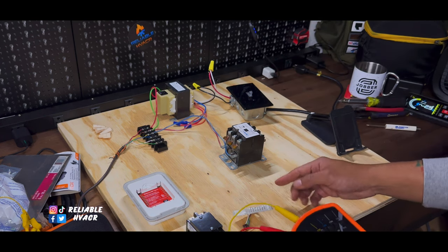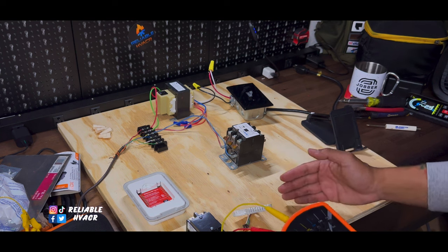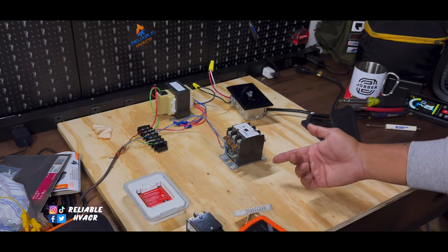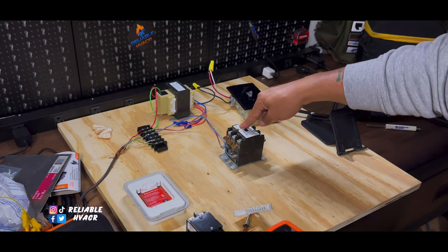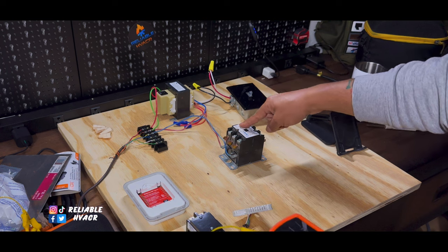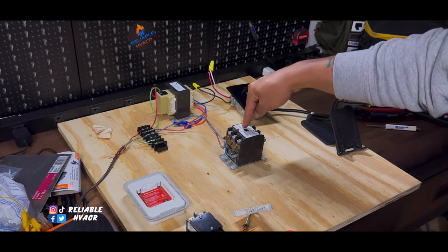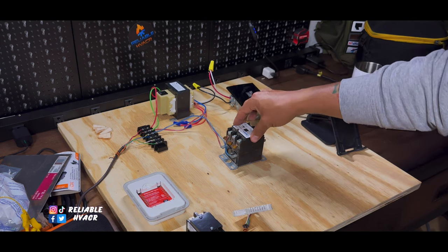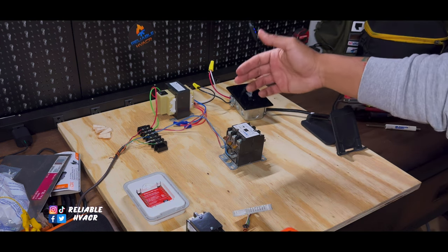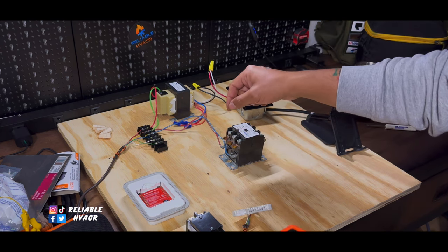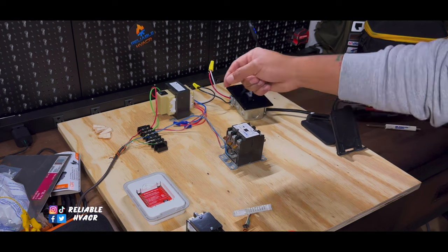Normally, I'm suspecting issues with the compressors. Compressors themselves, wiring with them, or their contactors. It was shorting out immediately, because I think they had the fan on. So, this was what kept tripping our transformer. And it was immediate, and I had to go on there, and I had to disconnect everything, and check the coil resistance, and find out that way.